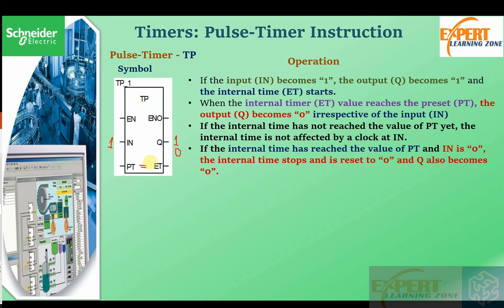Even if the input state has changed to zero or one within that duration, the output will still go to zero. That is why, if the timer has not reached the preset value yet, the internal timer is not affected by any event on the input parameter. Lastly, if the internal time has reached the preset value and the input IN is zero, the internal timer stops and resets to zero and Q becomes zero. It checks the state of the input only after the preset time equals the internal time — if it is one, it will begin again; if it is zero, it will reset.